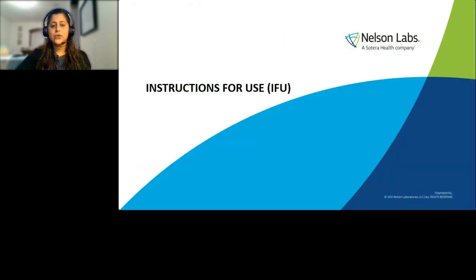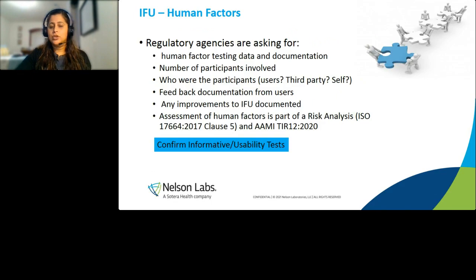Our instructions for use. Human factors play a huge role in instructions for use. They are the first people that we have to worry about. Users are most important in this. We have to make sure that they understand how the instructions are written. And these tests are performed as well with the users. It is almost not a requirement, but highly recommended that you do perform human factors testing during your design file or your design phases of your devices to get feedback from the users.